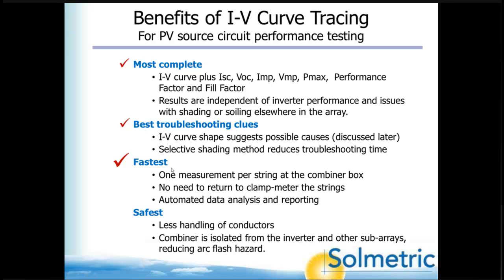The next driver for adopting curve tracing is that it's the fastest measurement. And the reason for that is that it's one measurement per string at the combiner box, and there's no need to come back later and clamp meter the strings when the inverter is operating in order to find out what the operating current is. In addition, data analysis is automated by the Solmetric data analysis tool, and it generates a really professional looking report. And a lot of people point out to us that the measurements are fairly easy for them to make. It's the data analysis and reporting that is quite time consuming. And that tends to be a little bit more expensive labor too. So speedier is not just the measurements themselves, but the whole process, saving time in the whole process. So a quick tour of that point.